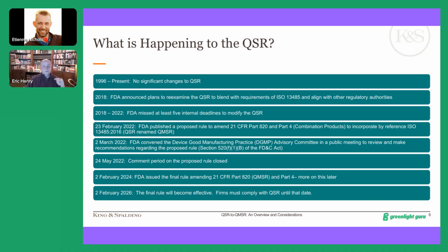period. We want to note here too, and I'll mention this again shortly, that the FDA will not enforce the QMSR until February 2nd, 2026. On February 1st, 2026, you will still be complying with the current quality system regulation. And on February 2nd, you'll be complying with the quality management system regulation. And it's a hard switch. That's the effective date. But we are obligated to comply with the existing 21 CFR Part 820 up until that time.